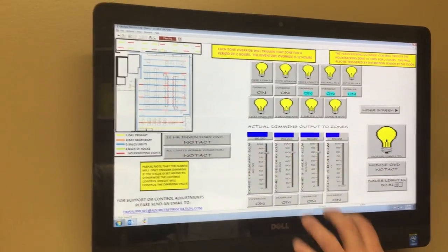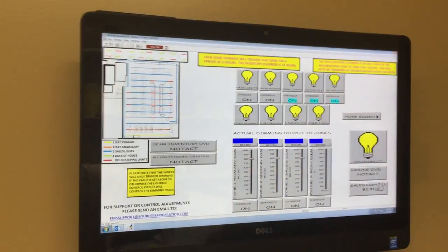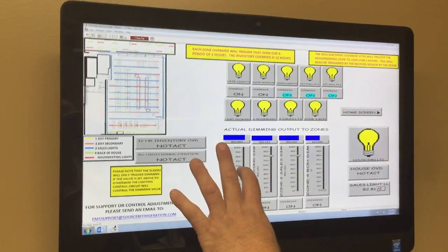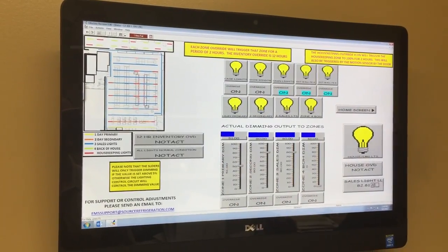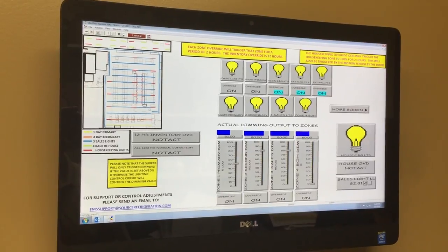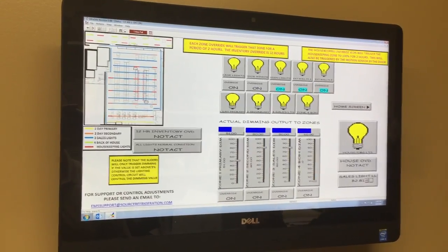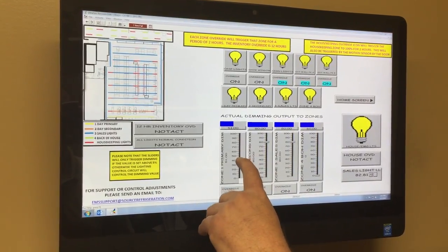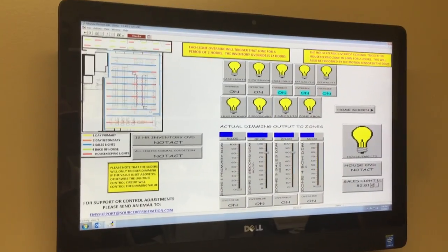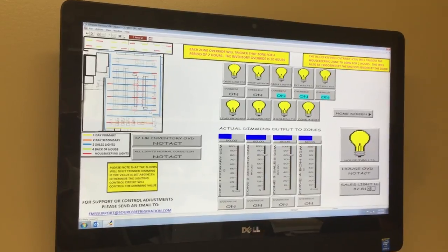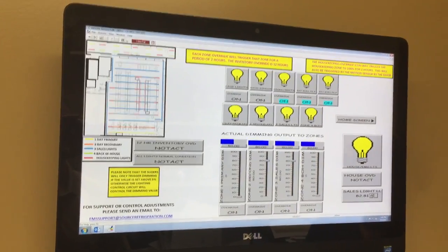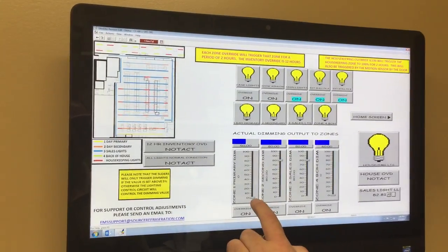money. The four sets of sliders here will actually control and dim the lights based on what you like in your store. It's required dimming control by the new regulations. Normally, all of these will be in the zero position, which allows for automatic control. In other words, when it's bright outside, they're going to start dimming down a little bit. When it gets darker at night, they'll go back up. So that's full automated control when it's at zero.